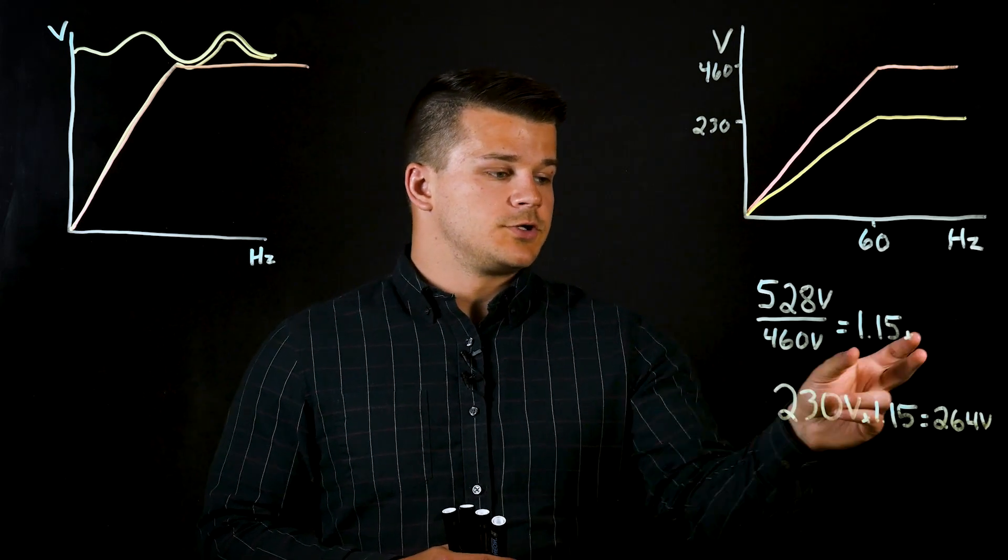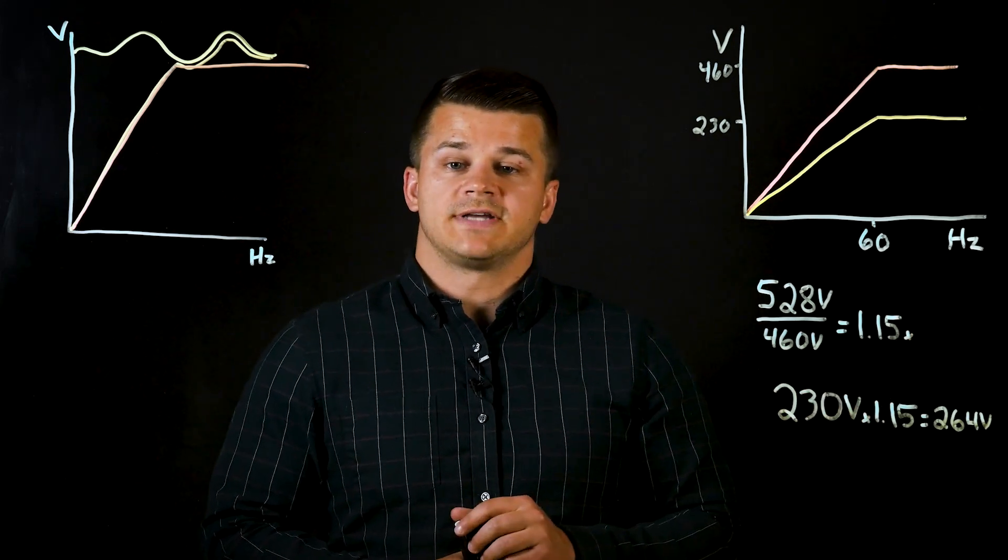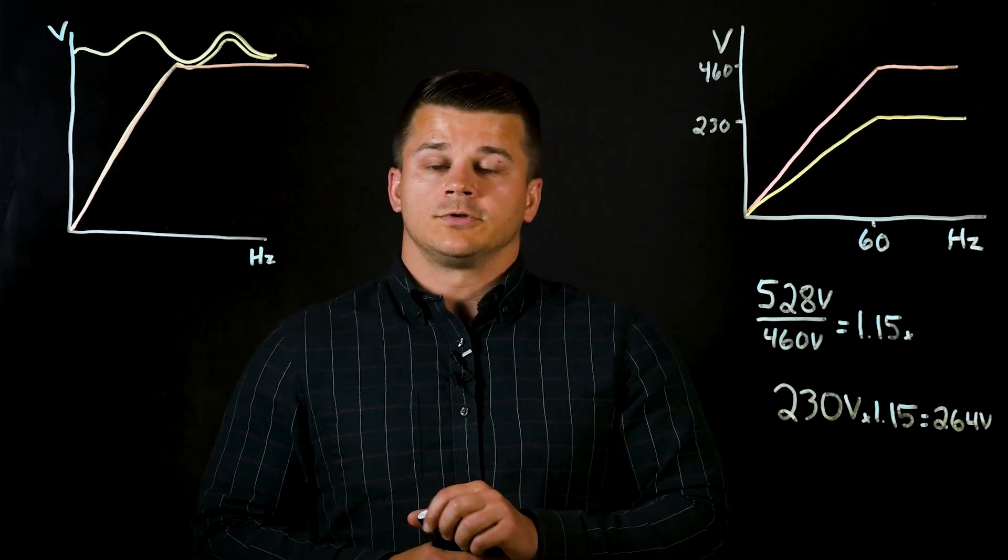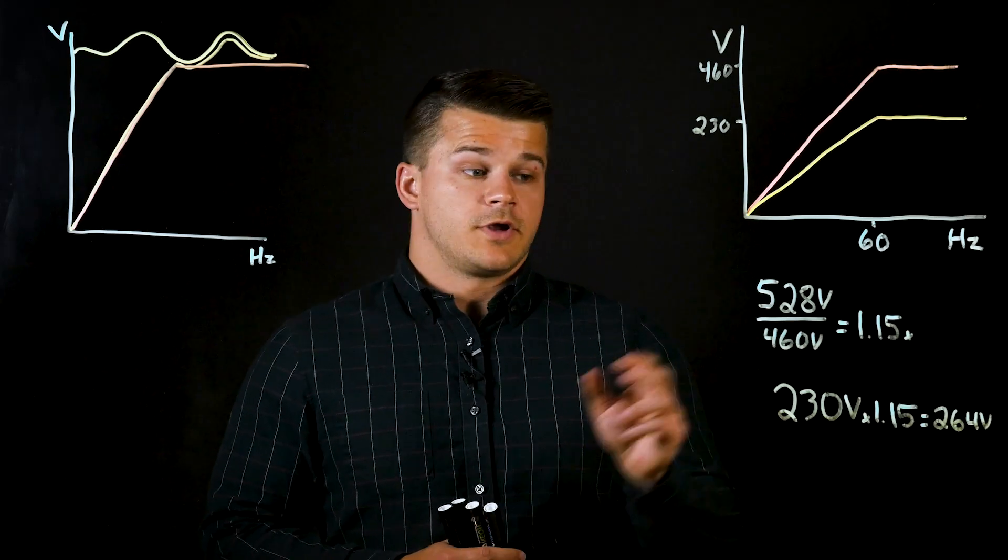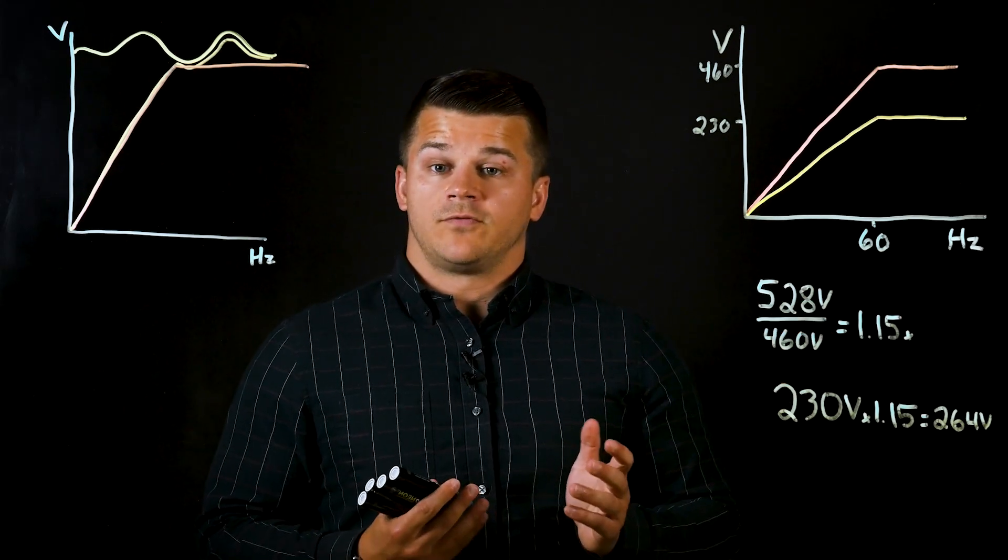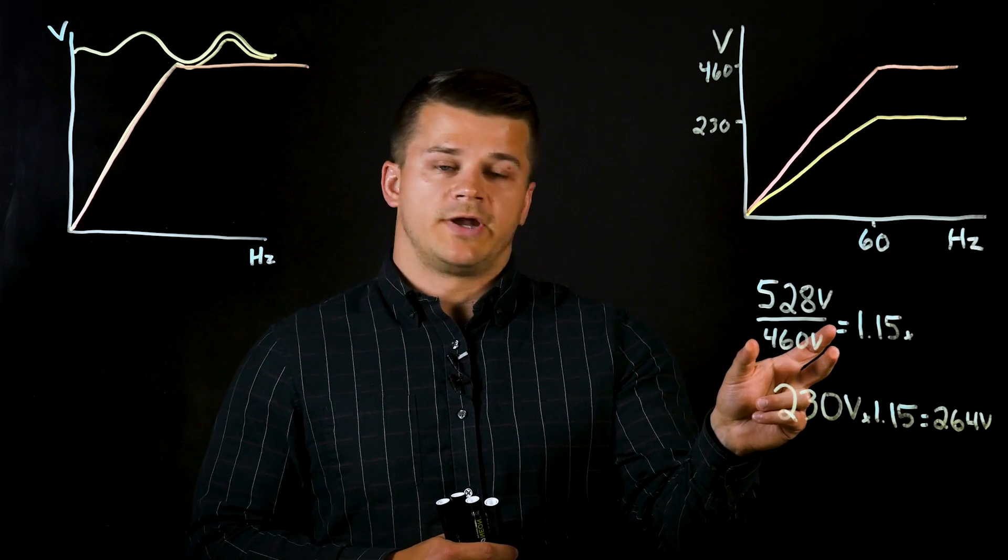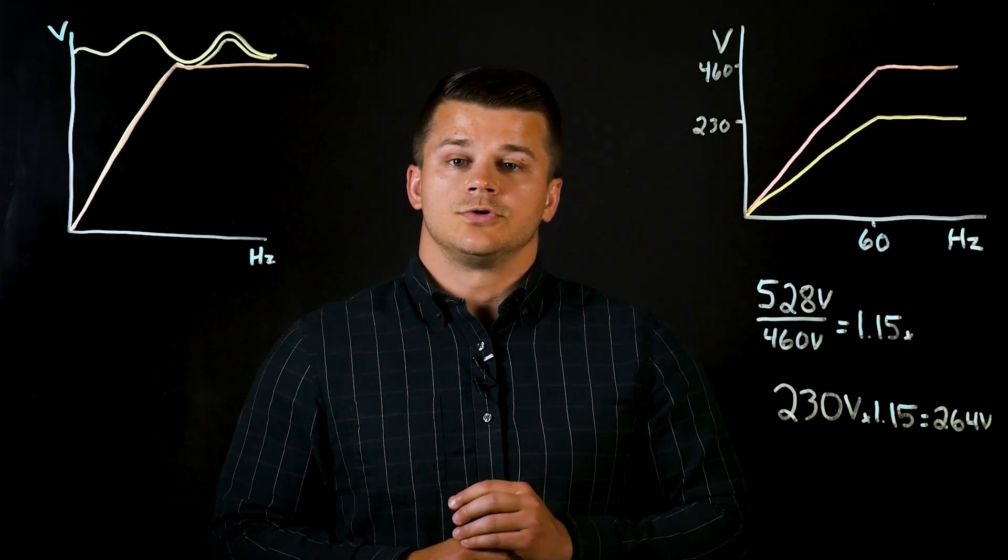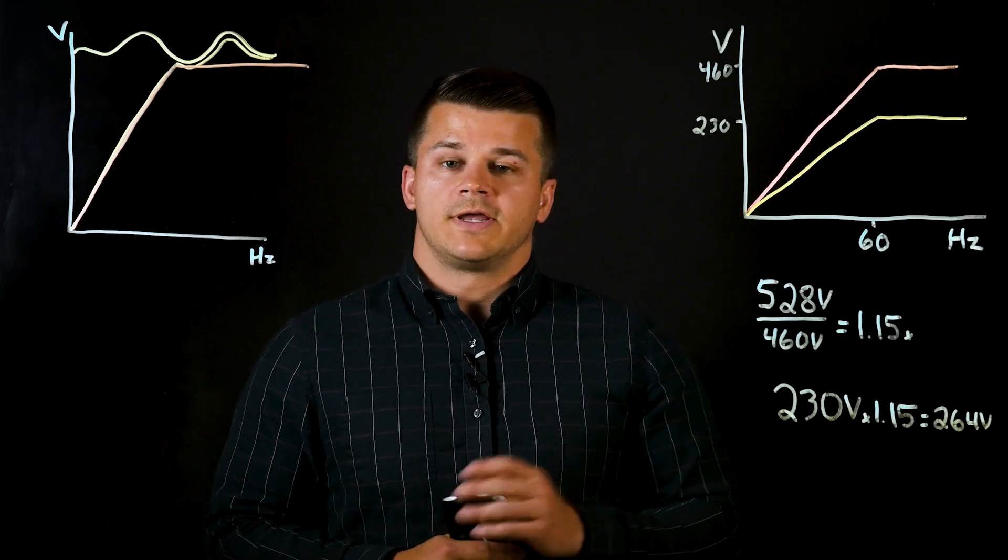So if we divide these two numbers you can get up to 1.15 times higher than the motor's rated voltage. So without the voltage stabilization function, if your input voltage reaches up to this 528 volts, the drive will simply be outputting that voltage to the motor rather than its rated 460 volts. This increased voltage can lead to premature failure and overheating of the motor.